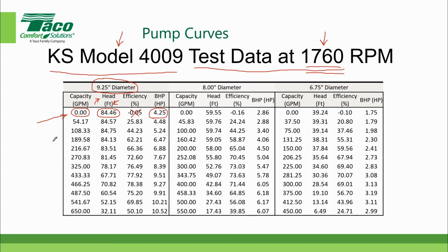And the thing that's important to recognize is that as the flow increases, we go from around, say, 0 gallons per minute up to 650 gallons per minute, look what happens to the horsepower. The horsepower also increases. So there's a relationship between horsepower and flow. And we'll talk about that in a little while.